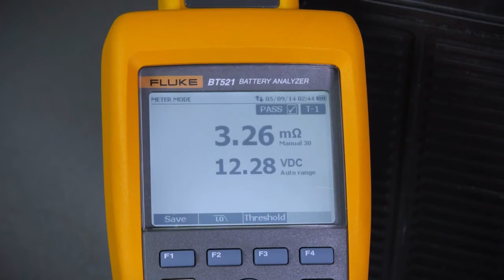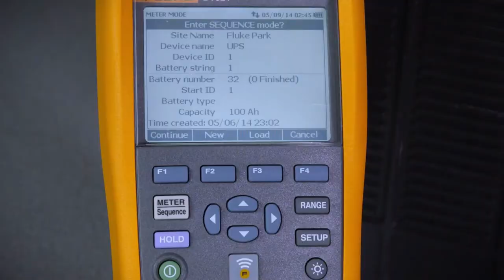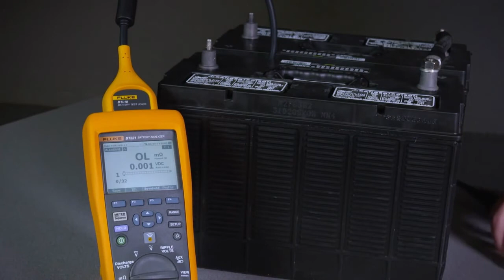Sequence mode allows you to take and store multiple measurements simultaneously. We've created a sequence name for this site, which is Fluke Park. Our device name is UPS. For the purpose of this demonstration, we'll assume we have 32 batteries in this string, supplying power to the UPS. Press the Continue button. You'll see that the first space in the memory is ready.